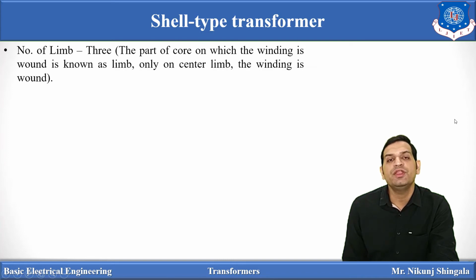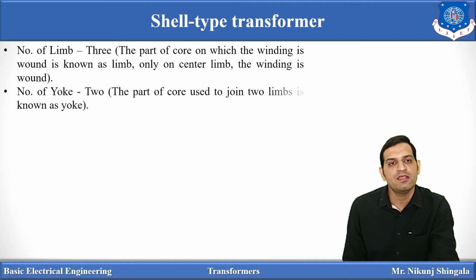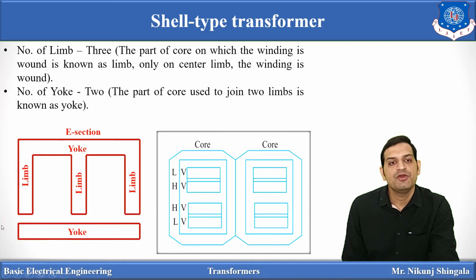So it consists of three limbs. The windings are placed on the central limb. Limb is a portion on which winding is placed, and yoke is a portion which is used to join the two limbs. So here you can see E and I shapes are used to design the shell type transformer. It consists of three limbs and two yokes. Yokes are basically used to connect the limbs.